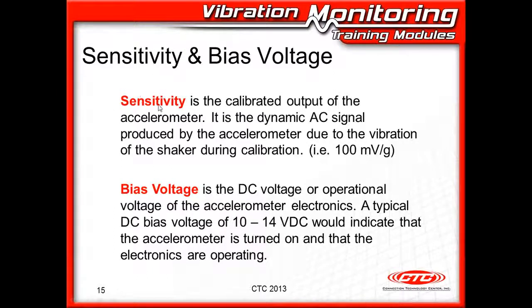Looking at our outputs, we actually have two outputs on an accelerometer. One, the sensitivity. This is the usable output. This is what you guys are using to develop your FFTs and your time waveforms. It's the dynamic AC signal. When we put this on a shaker, we would call this the calibrated output. It would also have a sensitivity tolerance.